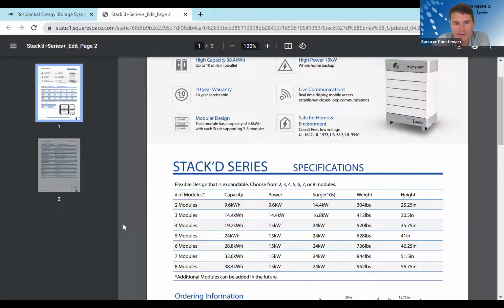So you want at least the 14.4, and usually the 19.2 is what we're seeing. I'd account for anywhere from a third to a half of the daily consumption from the homeowner's average daily consumption, and that's a great sizing method for the battery.